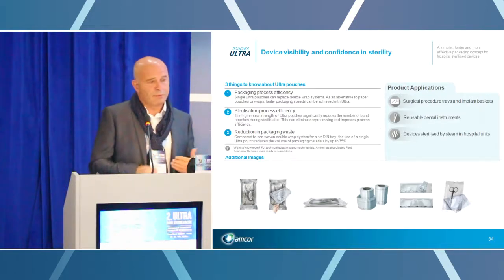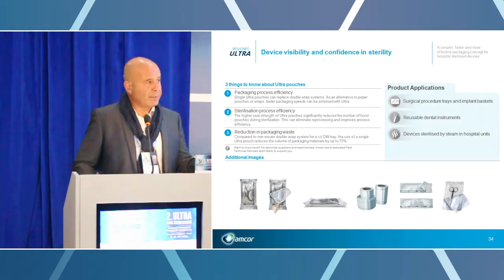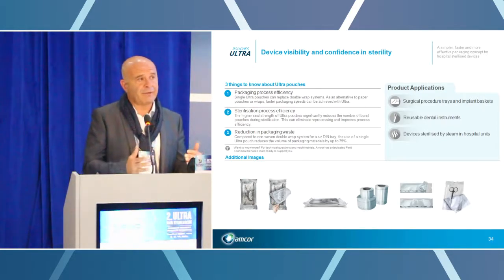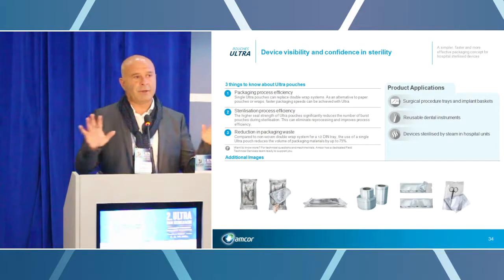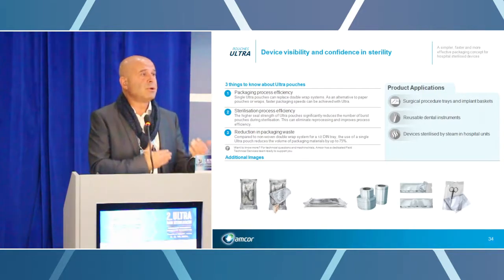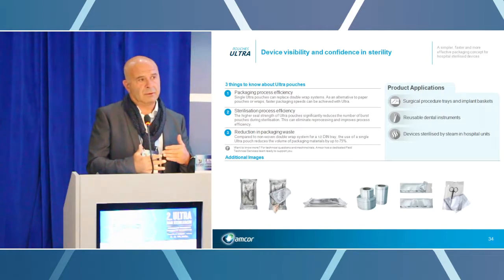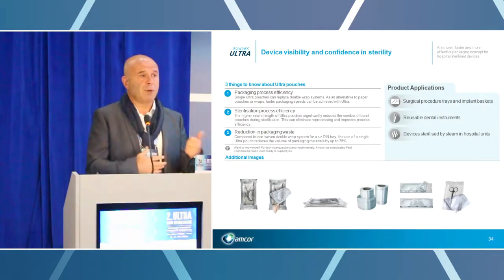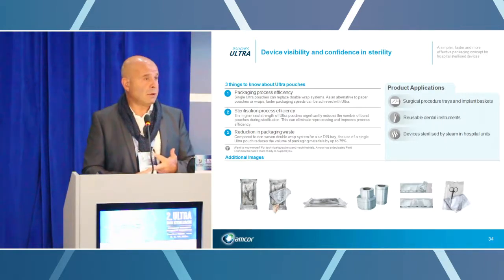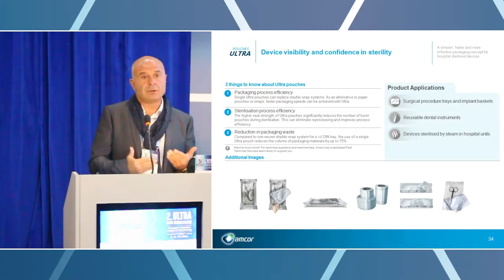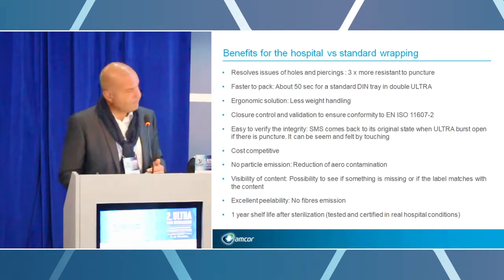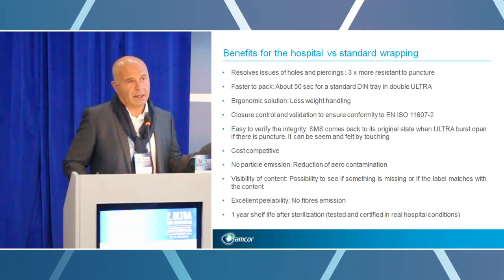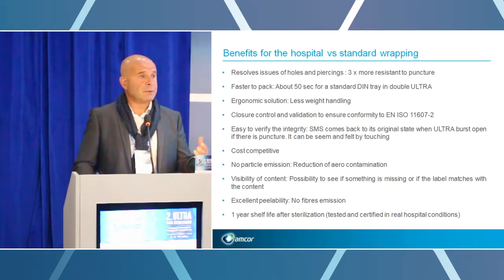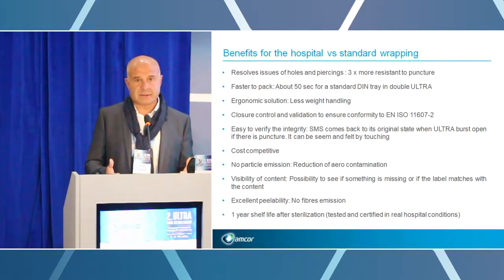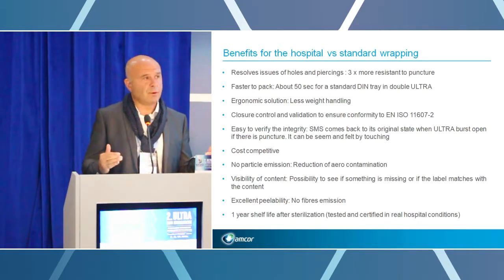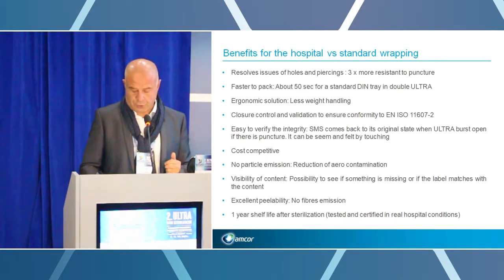This is the comparison with some other packaging like wrapping, but it depends. I think it's not possible to have just one packaging that is better for all. But for the CSSD, it's very important that you analyze what the risk is, and in function of the risk, you use wrapping, you use pouches and reels, you use paper or a strong-resistance material. It depends on the medical device you put inside. It's the same for the container. You have some advantages, but we know that for some instrument trays, the container is the best solution. Okay? We don't have a best solution for all. It's your choice in function of the risk.